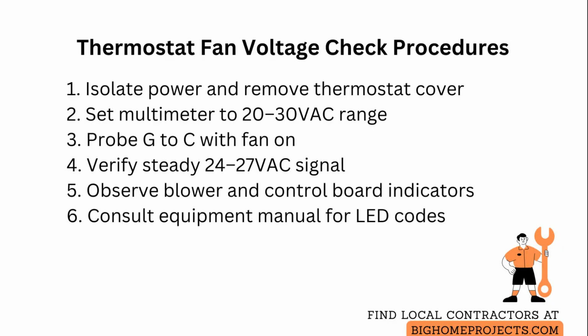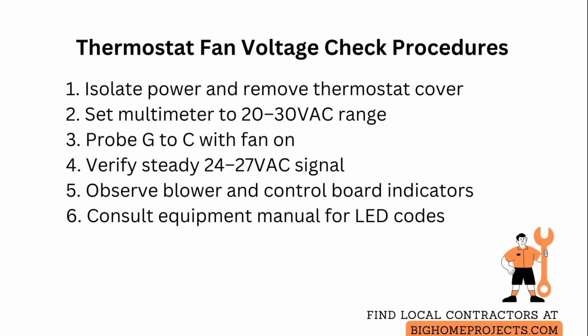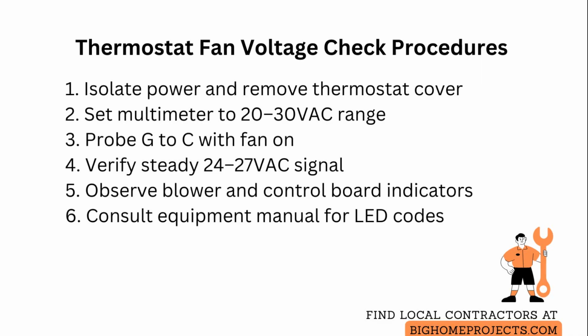Fourth, if voltage is present but the blower does not run, test the blower by supplying the same 24-volt signal directly at the blower relay coil terminals to determine whether the relay or motor is at fault. Avoid powering the motor directly from line voltage without proper knowledge.